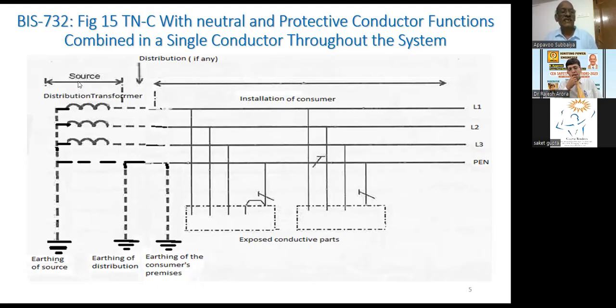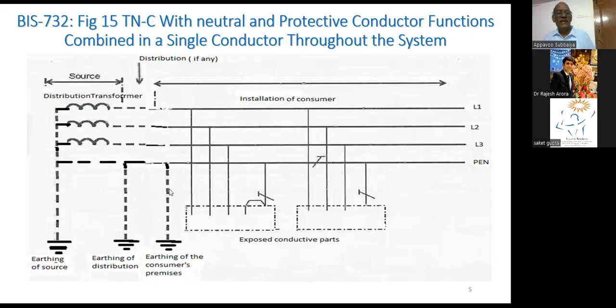Here you can see that this is a source, this is a distribution, this is a consumer area. And the PEN is protective earth neutral. This is also known as the protective multiple earthed, PME, conductor. So the protective conductor is earthed at multiple locations to reduce the overall combined earthing value for the suppliers, to avoid any high voltage impressed on the consumer's premises. This is the objective.